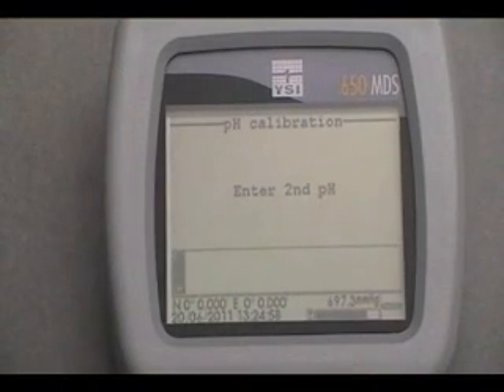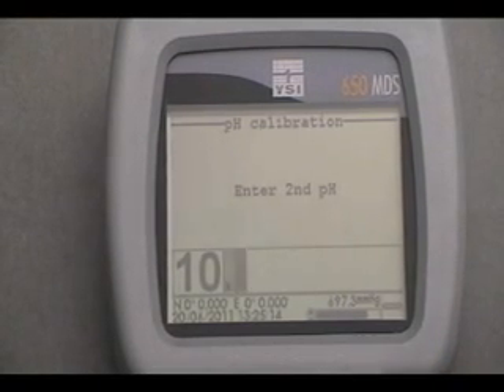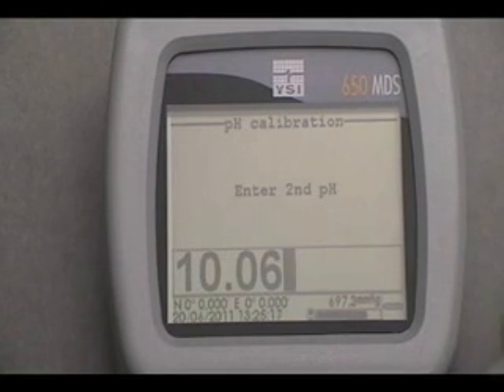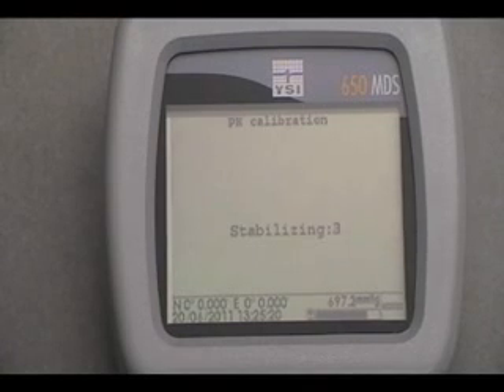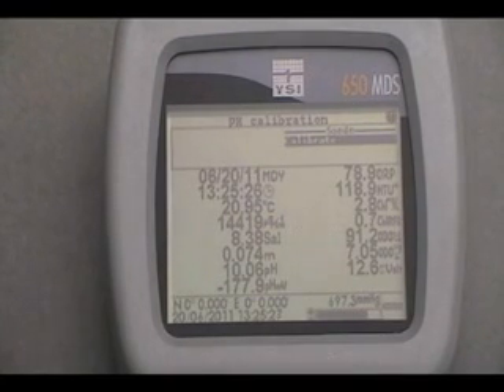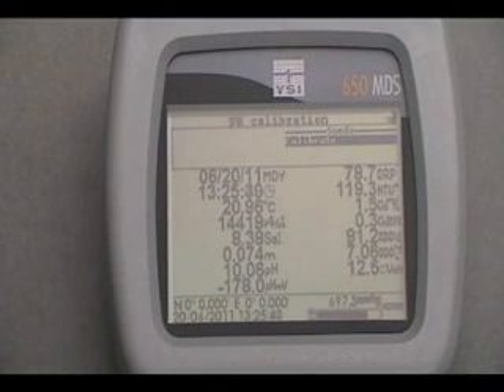Step 14. Input the value of the pH 10 solution at your calibration temperature. You can find this on the table on the standard bottle. In this case, we are calibrating at 20 degrees Celsius. The input value will therefore be 10.06. Press Enter. The values of all the sensors will appear on the screen and change as they stabilize. Step 15. Record the pre-calibration reading in pH units. Step 16. When the pH reading is stable, press Enter. The calibration will be accepted.